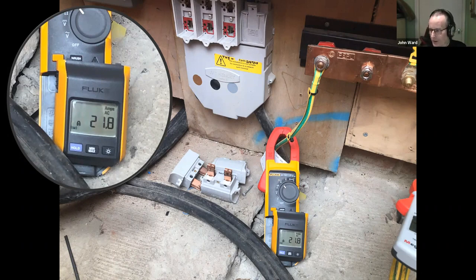Fine if there's no current on it, but as we see in this image, 21 amps there. If you've got something switching that in there, something could go very, very wrong in a nasty way. You've got a little tiny relay that switches that over, and there's going to be some kind of arcing. The first time it does it, it could just as easily be completely destroyed.